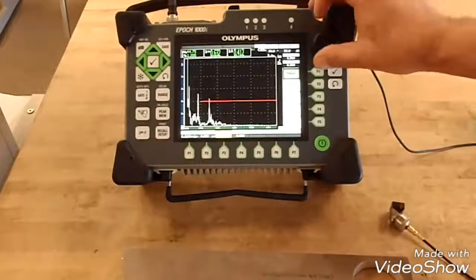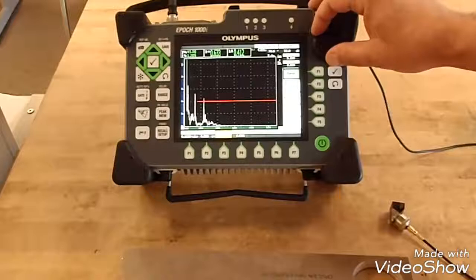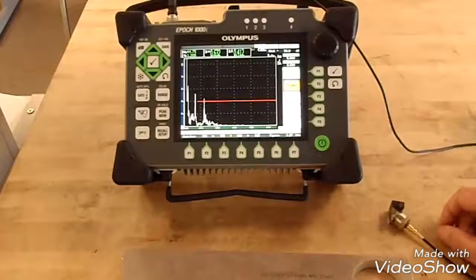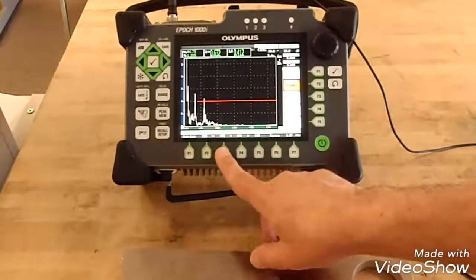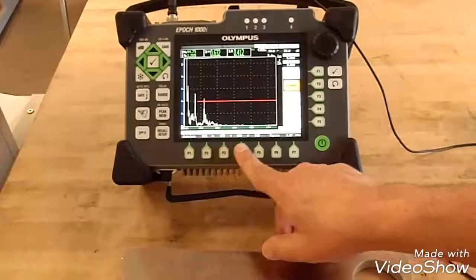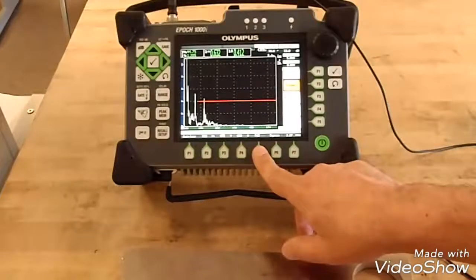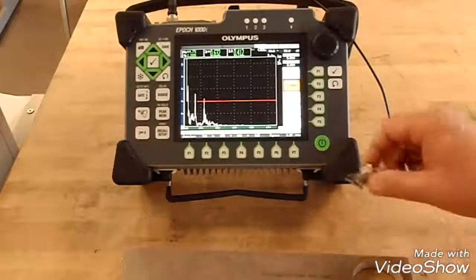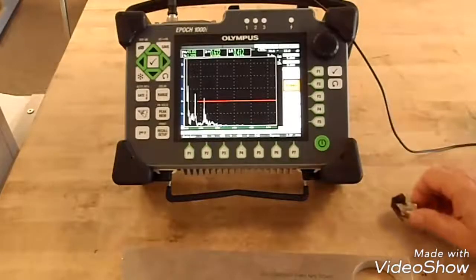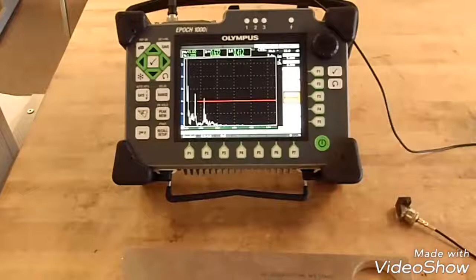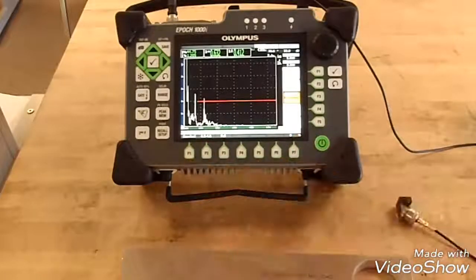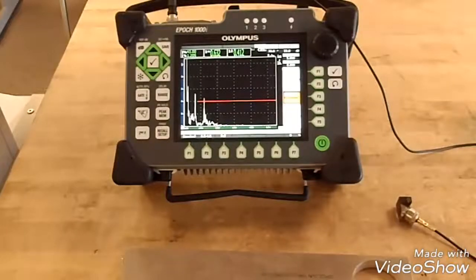Set your pulser to 475 volts. It's a pulse echo square wave. For two and a quarter megahertz, for the receiver: full rectification, zero rejection, and the filter of 0.5 to 4.